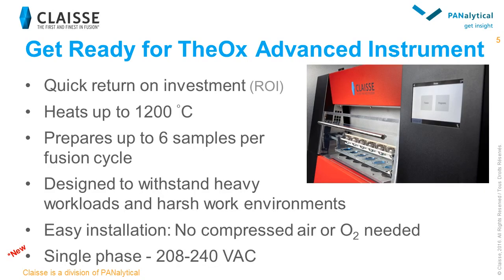As with its previous version, TheOx Advanced ensures a quick return on investment for the users. It can heat up to 1200 degrees Celsius. It is powered by electric resistance heating and can prepare up to six samples at a time. It is a fully automated fusion instrument — safe, simple to use, and designed to withstand heavy workload and harsh working environments.